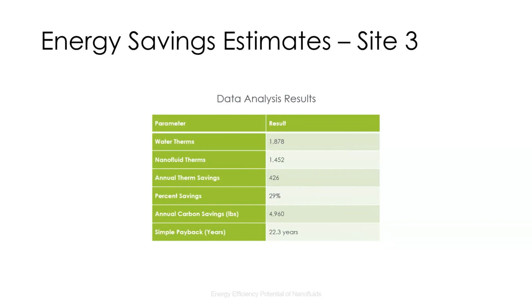Again, the building loads that the data indicate are far lower than we'd expected. The typical boiler loading based on the Minnesota Technical Reference Manual is about 12 times that of what we calculated at peak heating conditions in our analysis. Again, this ties back, at least in part, to some additional heating loads that weren't captured in our analysis, likely from those radiant heating panels.